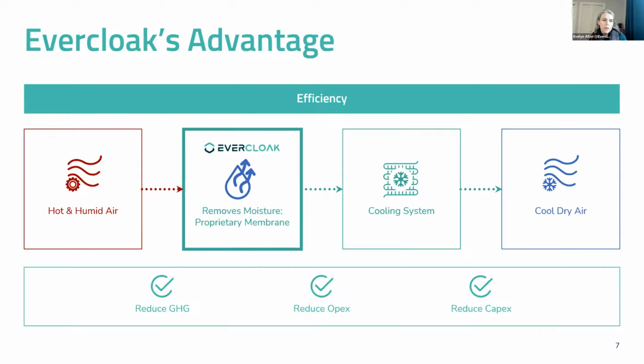So how does this work? Today's cooling technology uses vapor compression, which removes humidity from the room and cools the air temperature in one step, in the same process. It condenses the humidity, removing that latent heat, and drops the temperature in that process—often below comfortable, especially in very humid climates—so more energy is needed to heat it back up.